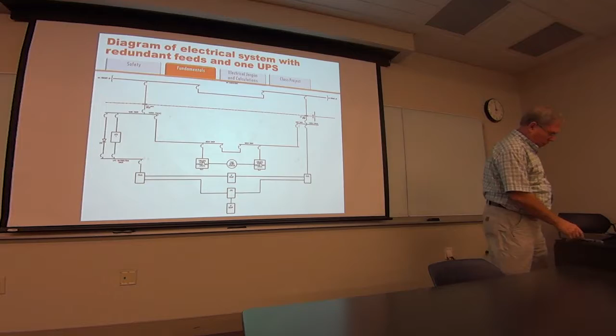Put a generator up here. And if you lose power on this bus, this generator will pick up and carry that. So you got yourself pretty well covered for any eventuality, right? Loss of power, power quality events, whatever. In the TVA system now, if you're in Los Alamos, they're in the middle of the desert. They got a line coming from east and a line coming from west. If they lose power, they have a tremendous amount of exposure up here to this. With us, we've got 5 161 lines coming in the substation. Unless TVA's system goes down, we're probably not going to go down.